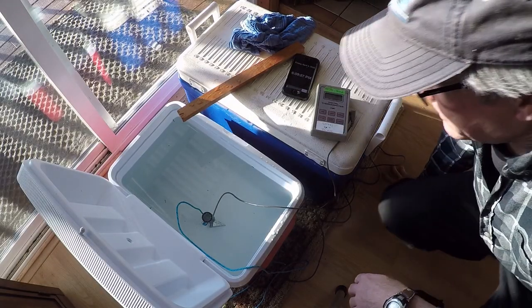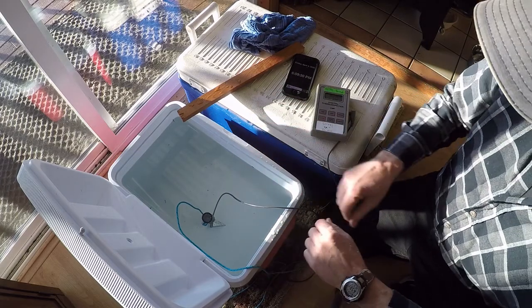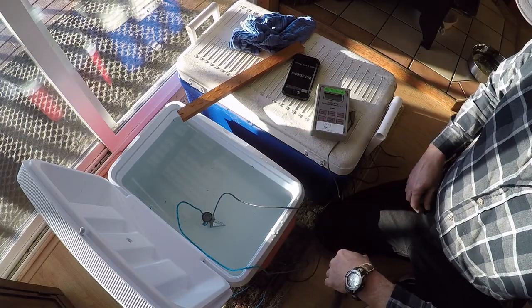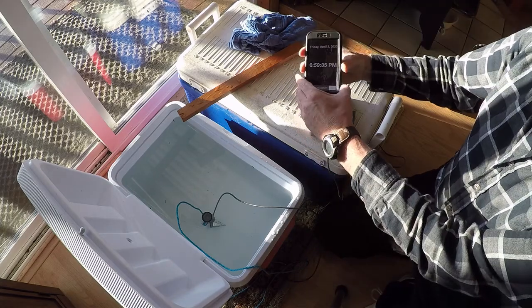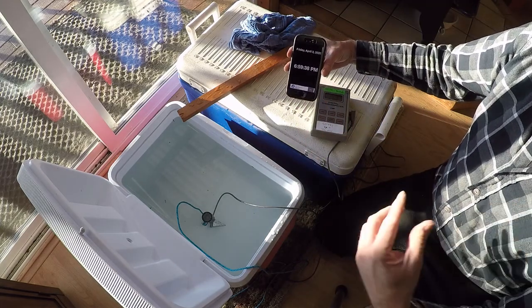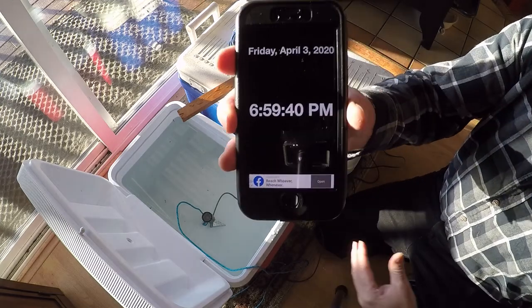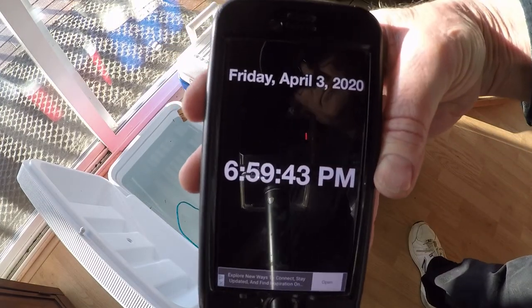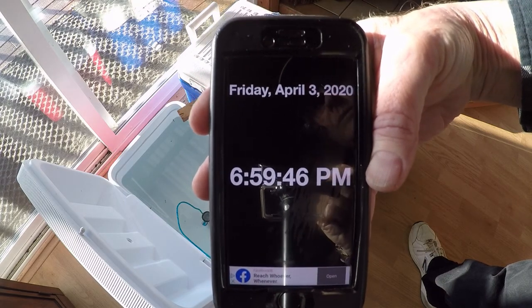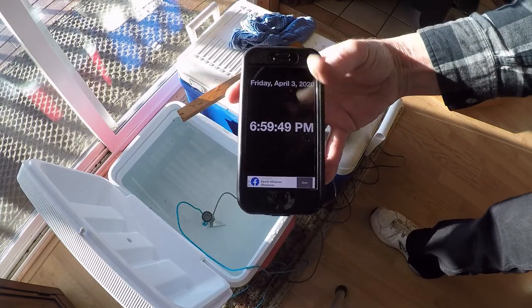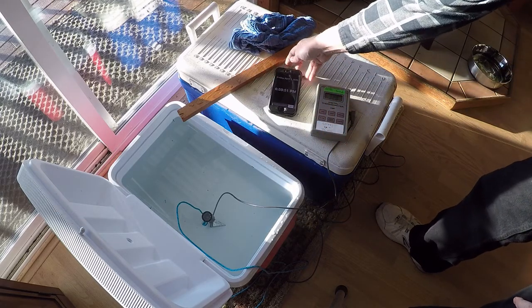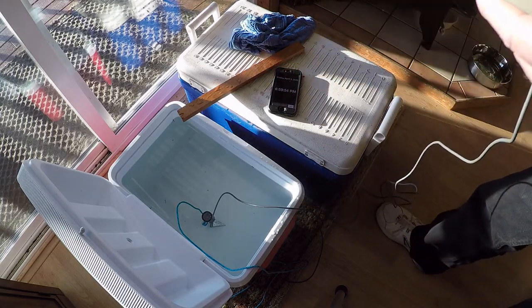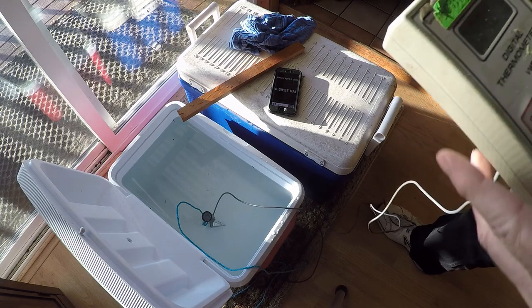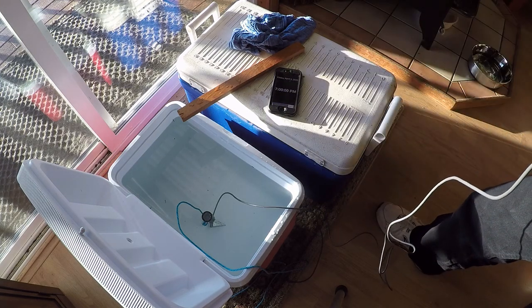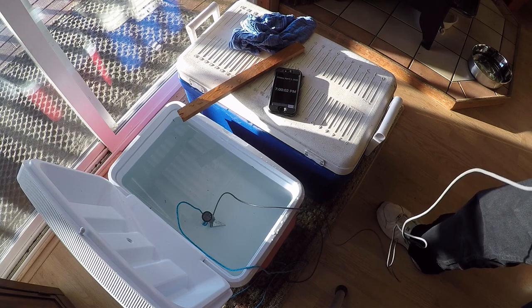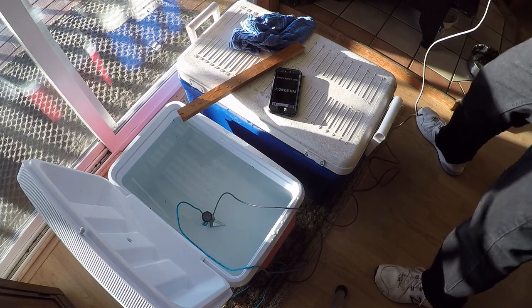Okay, so we've let the water stabilize and let the probe stabilize inside along with this. And if you remember right, we set this up on the calibration over on the computer. I made it so that the probe would read when my watch was at the 0 mark. So what I'm going to do is record the temperature on the NIST thermometer, exactly at the 0. So it's at 24.9 degrees.